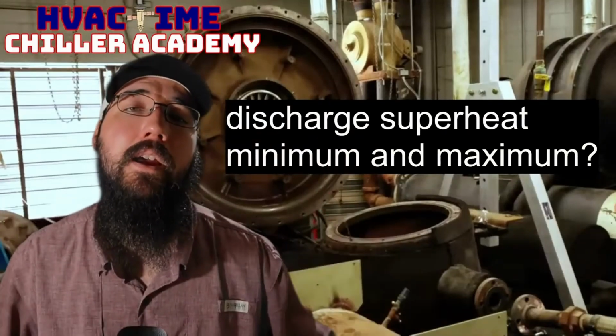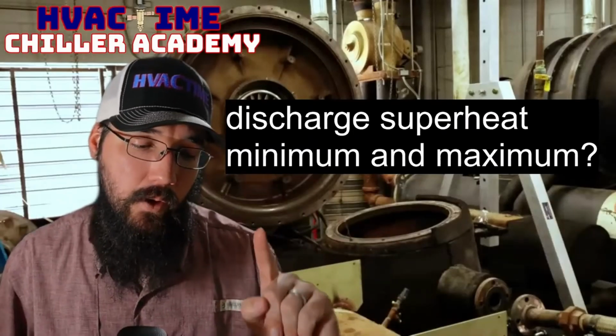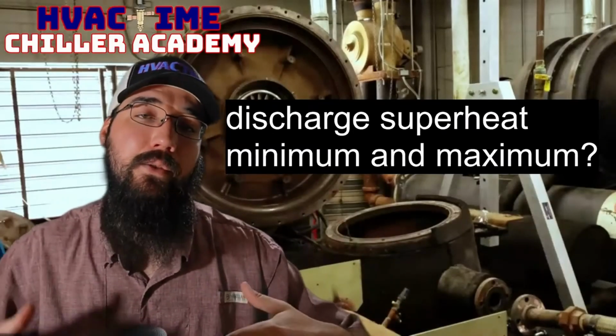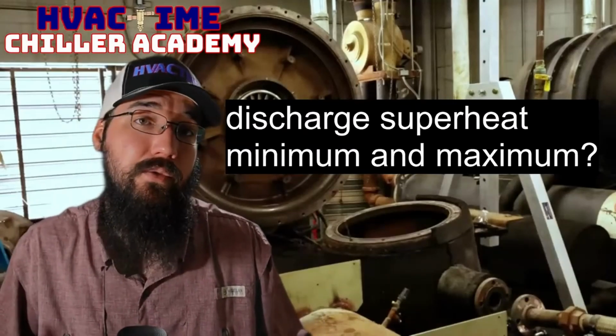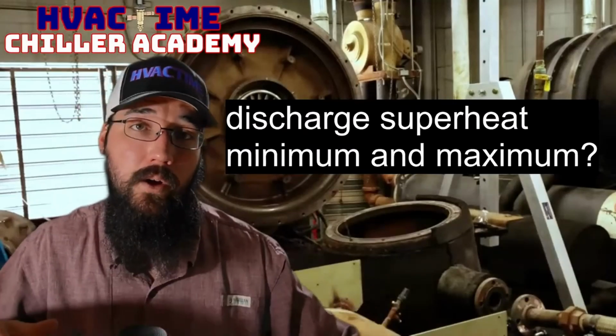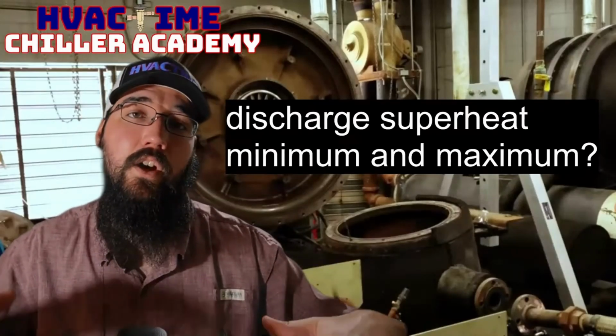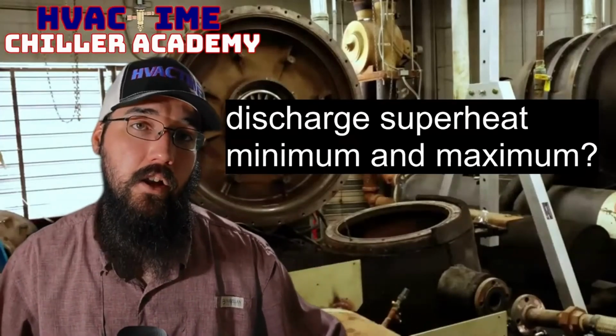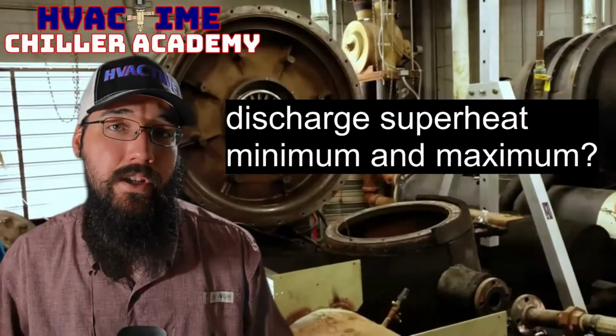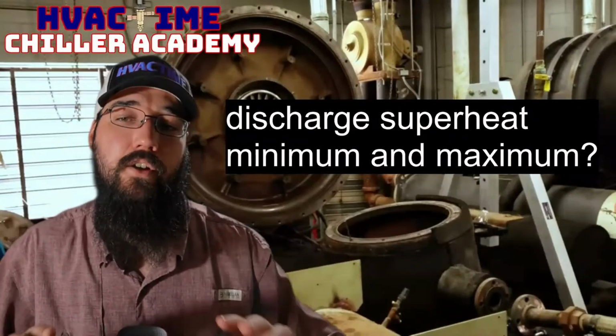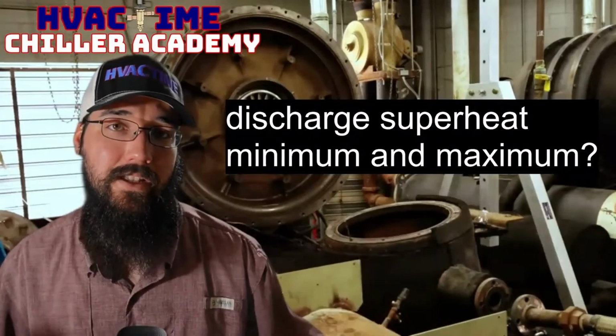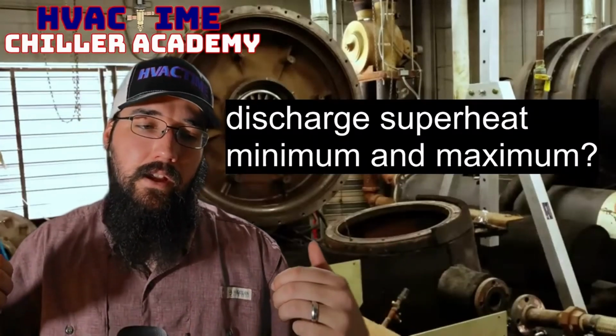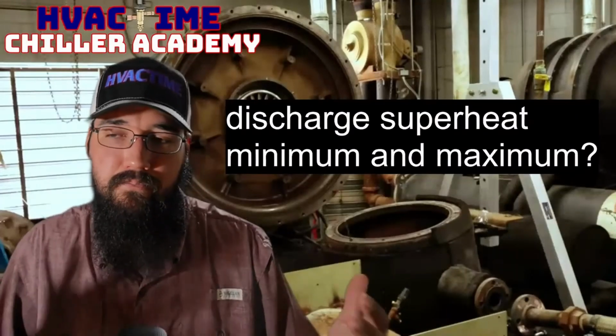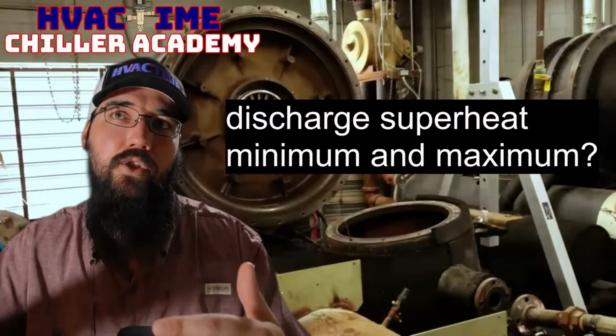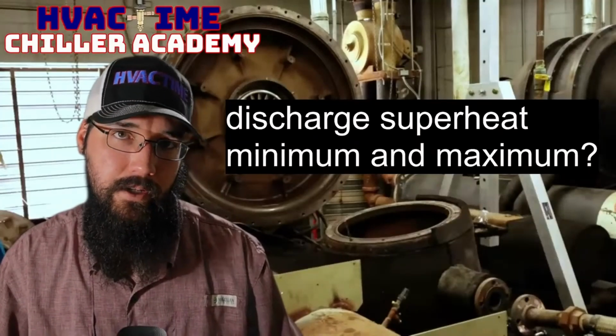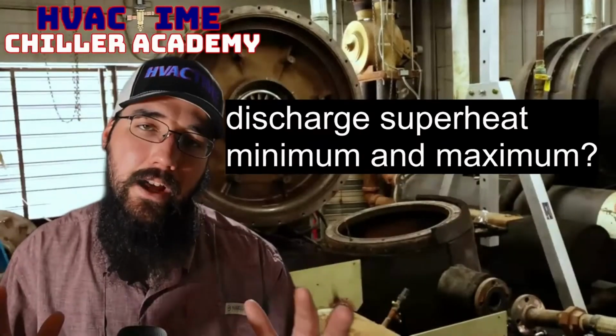And then as we load up, we should see that superheat go up. Now, there are some machines that, even with a pretty substantial load, may still run 15 to 20 degrees of discharge superheat, depending on how well they're tuned, and you won't see a whole lot of shift in that superheat from low load to high load. That just comes back to how well the machine was installed, how well it's configured, and its operating conditions at the time. So if everything's good, just because you've got a full load but you're running a lower discharge superheat, say 15 for example, doesn't mean you've got a problem.